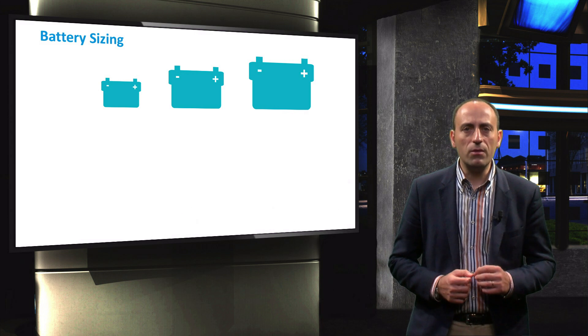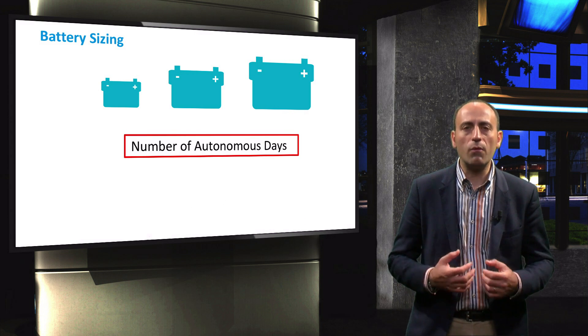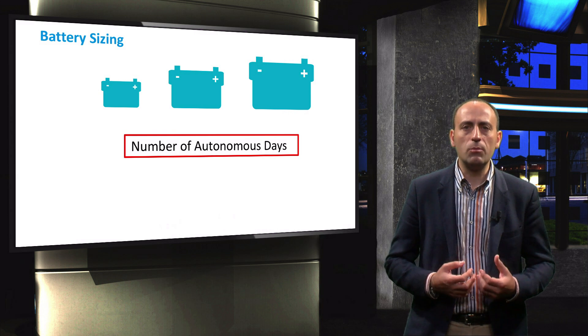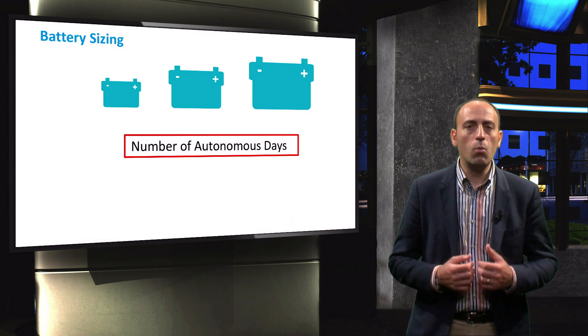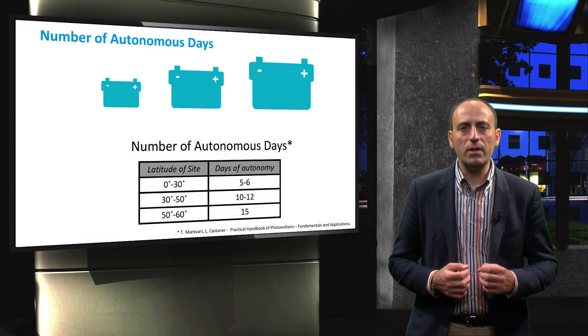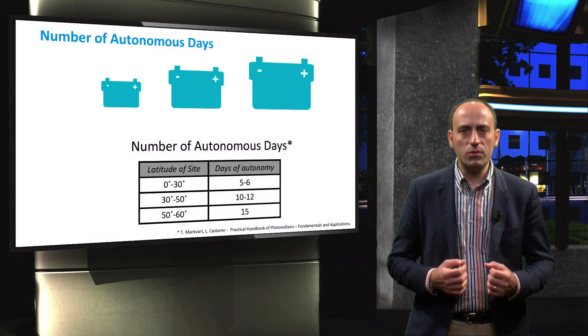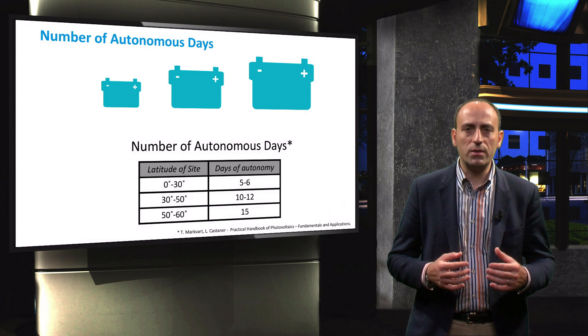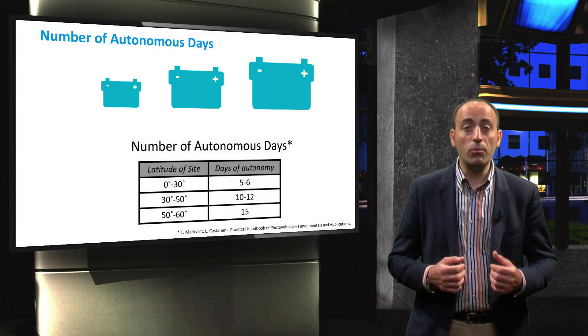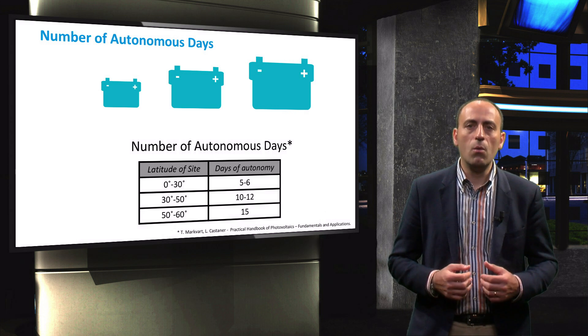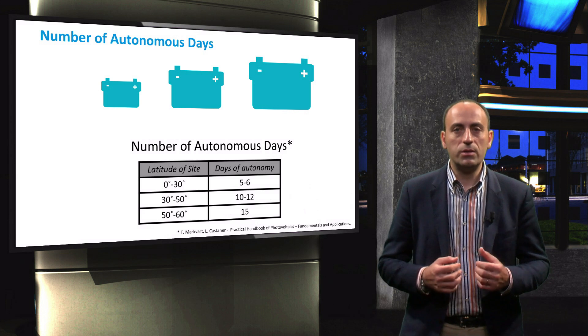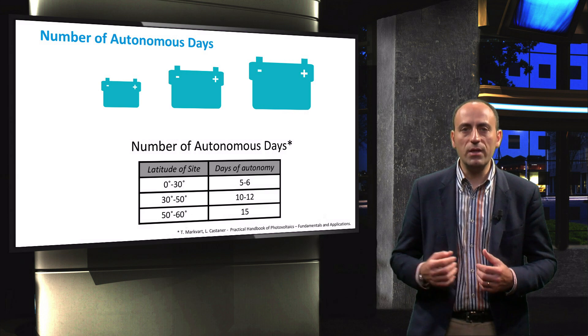A critical parameter for sizing the battery bank is the number of autonomous days. This is the number of days that the PV system should be able to power the loads without energy generation. The appropriate number of autonomous days depends on a number of factors. For larger PV systems, such as in a remote building or in telecommunication systems where the load demands are high, the number of autonomous days can be determined based on their location, using the following table as a guideline.